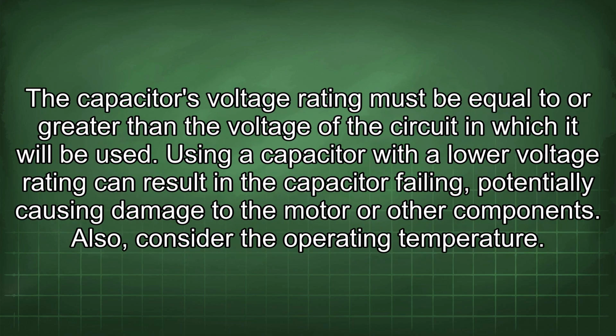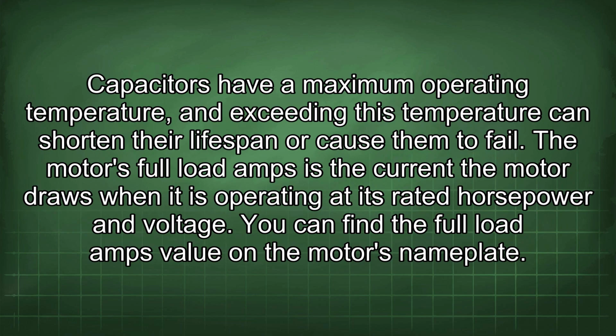The capacitor's voltage rating must be equal to or greater than the voltage of the circuit in which it will be used. Using a capacitor with a lower voltage rating can result in the capacitor failing, potentially causing damage to the motor or other components. Also, consider the operating temperature. Capacitors have a maximum operating temperature, and exceeding this temperature can shorten their lifespan or cause them to fail.